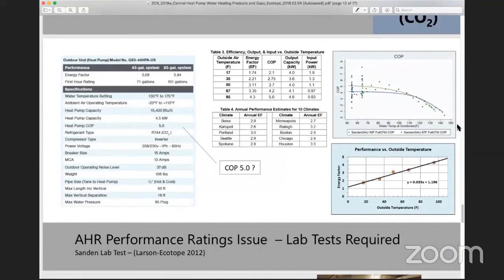So this slide's really important, and I just wanted to show this. These are the lab tests that Ben Larson at Ecotope did for NIA, and this is showing the Sanden spec sheet. Over on the left it says COP5, and we do see COP5, but only at one point. If you look to the right, you can see the curve as a function of the entering water temp for two different outside temps.